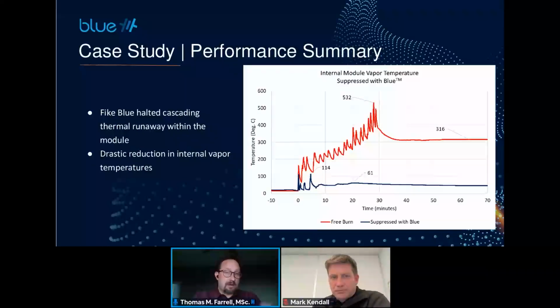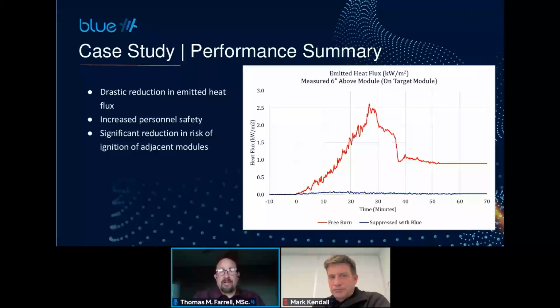And this is all good. And then the question is whether or not, even though we still had a thermal runaway event, that makes a difference to a neighboring module, and whether or not it can be triggered to go into thermal runaway in one of these cases. And so we're measuring heat flux above, from the module above, for this particular test. And if we look at that particular data, the results are stunning.